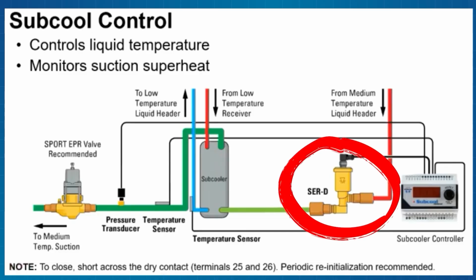All right, it's going to see the superheat climb because I'm not flowing refrigerant. It's going to slowly, over time, because it's looking at my liquid line temp and seeing that it's cold, so my PID is going to say, do this very slowly, right? Do what? Open, right? So my electronic valve is going to try to maintain that superheat. It's going to open very slowly, it's going to keep adding a percentage, add a percentage, add a percentage. Okay? So how far? All the way to 100, until we hit either a programmed stop or 100%. The valve's probably going to 100%, right?